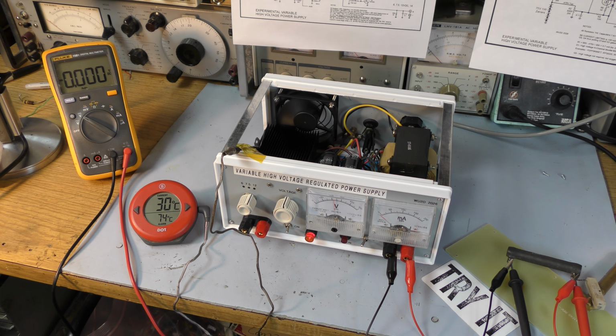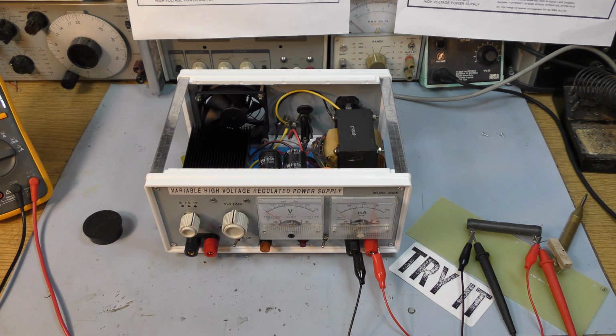Okay, now after about 4 minutes, it's starting to go down. Looks like the fan will turn off soon. Again, this was an overcurrent condition at 300 volts, putting out 20 watts constant, and the fan was really not able to keep up with it. So there are several ways to solve this fan issue. One would be to have a more effective fan, definitely putting the air right on the fins. Making a wind tunnel forces the air through the fins and out the exhaust fan.